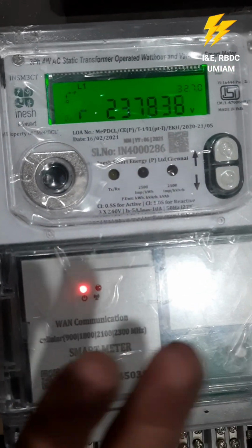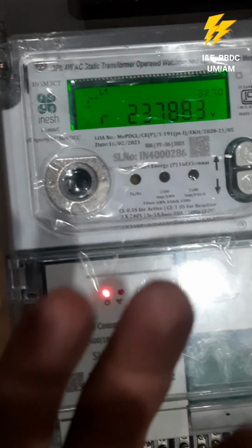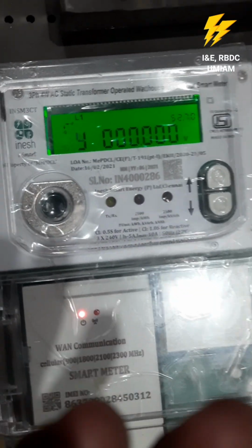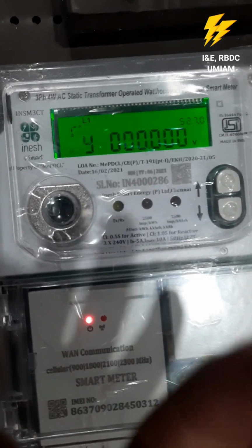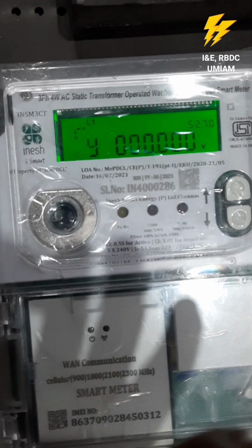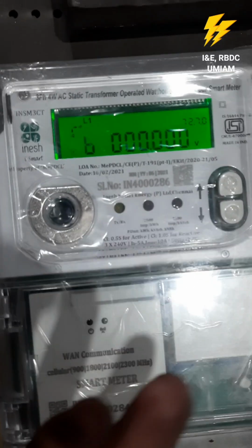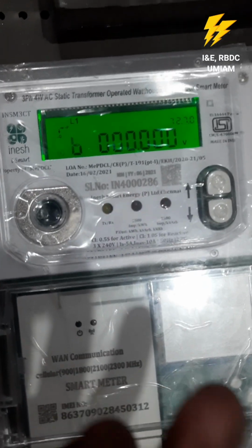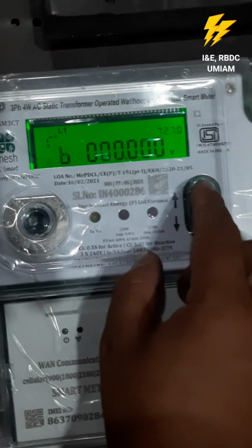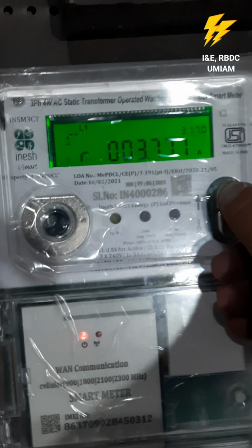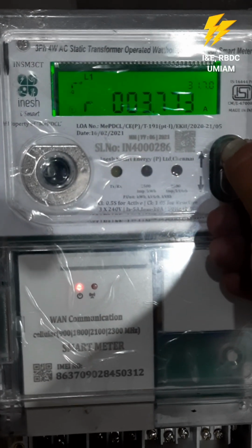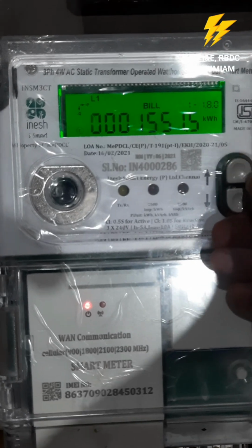But if you want to look at the maximum demand, which is actually required for HT consumers, because you have to take that also into consideration for billing purposes. For example, if the billing is done manually, then the demand is needed, because you have to apply Section 126 of the Electricity Act, that is, the excess demand charge will be there, which is twice the normal tariff. Now I'll keep this long press, then push. Yes, it has come.